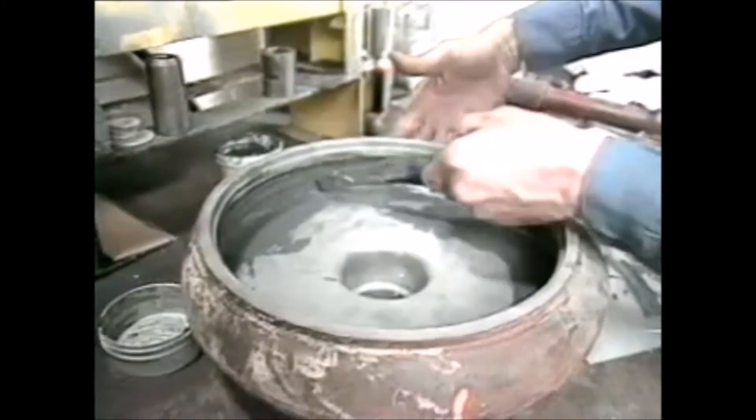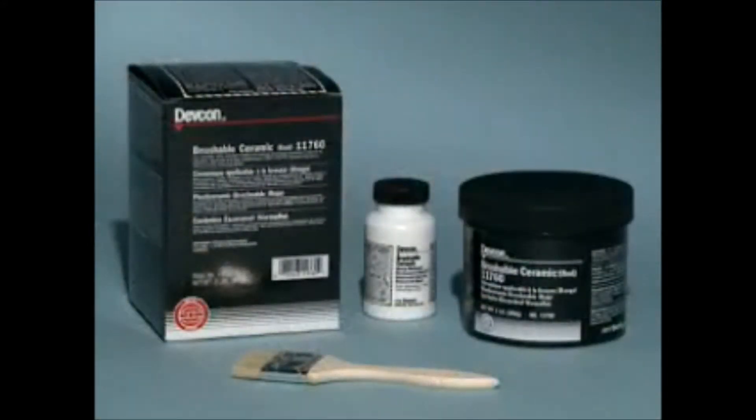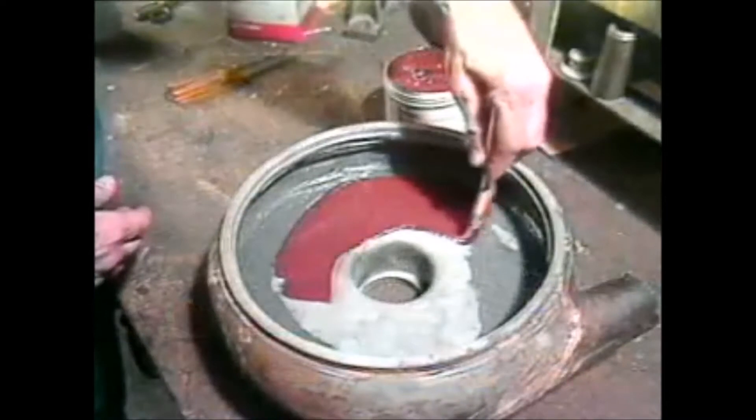To protect the area from corrosion, pitting, and cavitation caused by aggressive environments and friction, apply Devcon brushable ceramic to the entire surface in a thickness of approximately 30 mils.